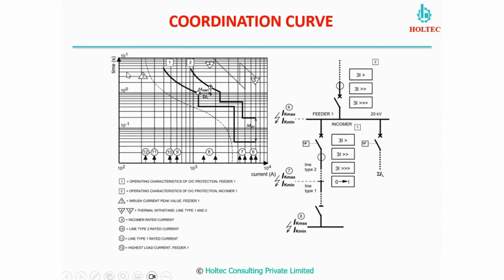This curve has the fault current on the horizontal axis and the time of operation on the vertical axis. In this particular network we have two relays, relay number 1 and relay number 2. For this fault, serial number 8, which is happening here, as per the principle, relay number 1 is our primary protection and relay number 2 has to be the backup protection. Here, for the entire range of fault current, we can find the coordination curve. So we know this is the amount of current in the fault. What should be the time of operation?